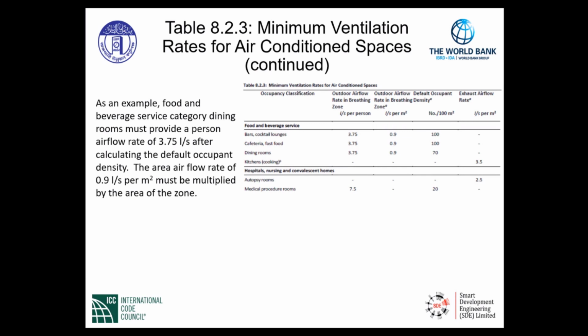As an example, food and beverage service category, dining rooms must be provided with a person airflow rate of 3.75 liters per second after calculating the default occupancy density. The area airflow rate of 0.9 liters per second per meter squared must be multiplied by the area of the zone. And the occupancy classification you can see here is food and beverage service. So what we're doing here is we are picking values from this table to integrate into an equation to ultimately calculate the total amount of outside air required for these particular spaces based upon the function of these spaces within our buildings.